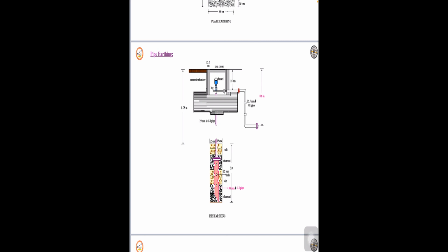The pipe has a much larger contact area with the soil so that it can handle larger leakage currents than plate earthing of the same electrode size. The earth wire, also made of copper, is tightly fastened to the earth electrode by means of nuts and bolts, as you can observe here in the GI pipe and how pipe earthing is carried out. Earthing is definitely beneficial whenever there is a fault or leakage current, so it is always advisable to use earthing. Hope you understood. Thank you.